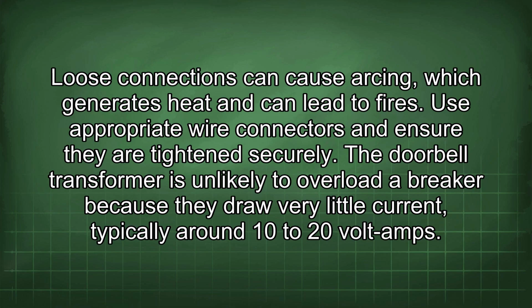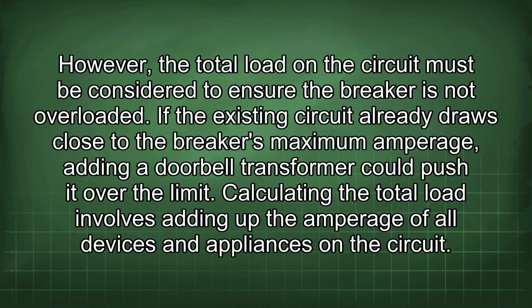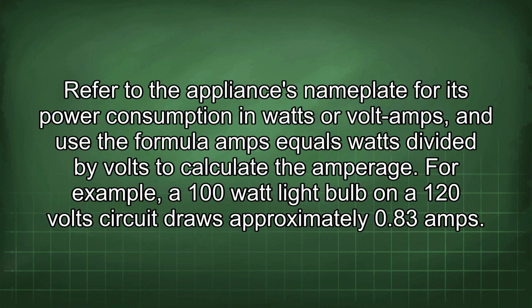The doorbell transformer is unlikely to overload a breaker because they draw very little current, typically around 10 to 20 volt amps. However, the total load in the circuit must be considered to ensure the breaker is not overloaded. If the existing circuit already draws close to the breaker's maximum amperage, adding a doorbell transformer could push it over the limit. Calculating the total load involves adding up the amperage of all devices and appliances on the circuit. Refer to the appliance's nameplate for its power consumption in watts or volt amps, and use the formula amps equals watts divided by volts to calculate the amperage. For example, a 100-watt light bulb on a 120-volt circuit draws approximately 0.83 amps.